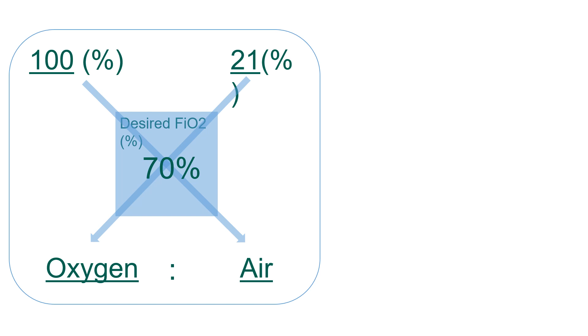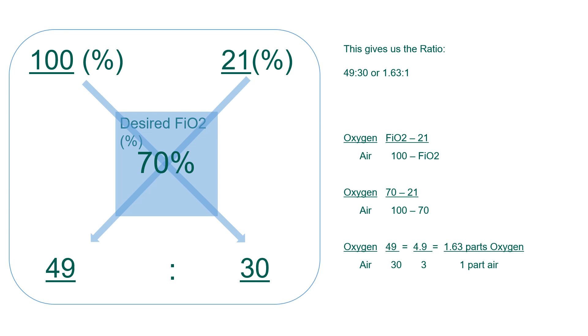So if we wanted 70% FiO2, and we have no way to mix gas with a blender, we have 100% on the left, that's your oxygen flow meter. You have a 21% compressed gas source on the right. Move it through, subtract each side, and there you go. That gives us a ratio of 49 parts oxygen to 30 parts air. And if you simplify that down to 1.63 parts oxygen to 1 part air, you will get 70%. And you don't need an analyzer, you just need 2 flow meters.